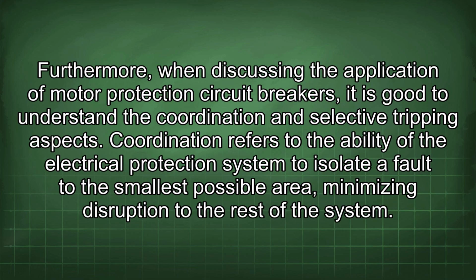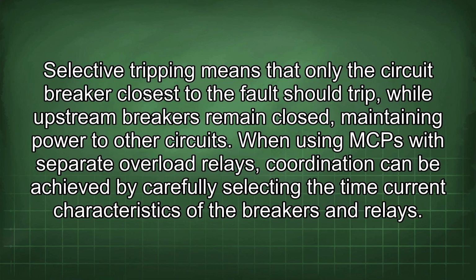Furthermore, when discussing the application of motor protection circuit breakers, it is good to understand the coordination and selective tripping aspects. Coordination refers to the ability of the electrical protection system to isolate a fault to the smallest possible area, minimizing disruption to the rest of the system. Selective tripping means that only the circuit breaker closest to the fault should trip, while upstream breakers remain closed, maintaining power to other circuits. When using MCP with separate overload relays, coordination can be achieved by carefully selecting the time current characteristics of the breakers and relays.